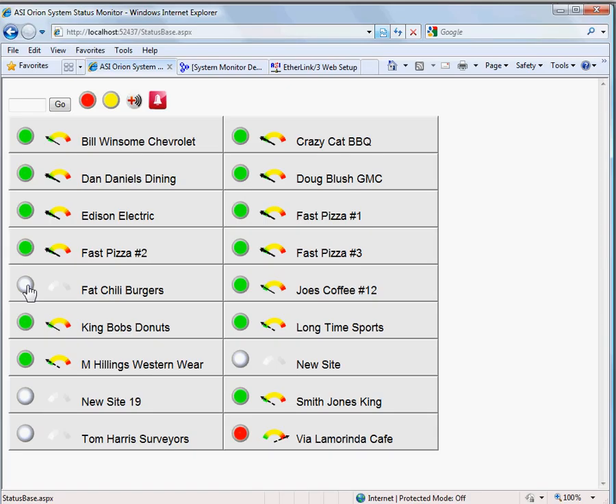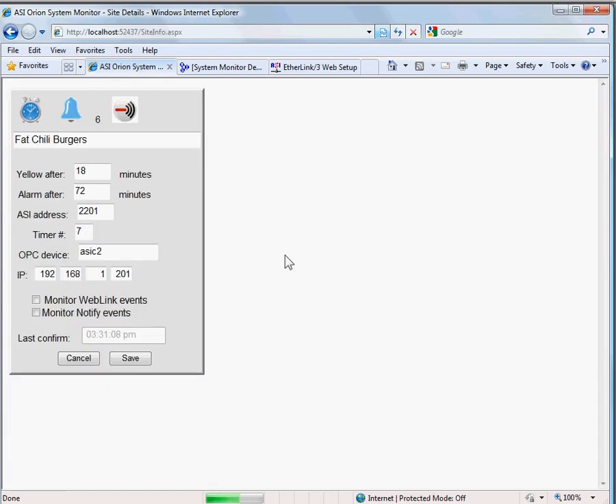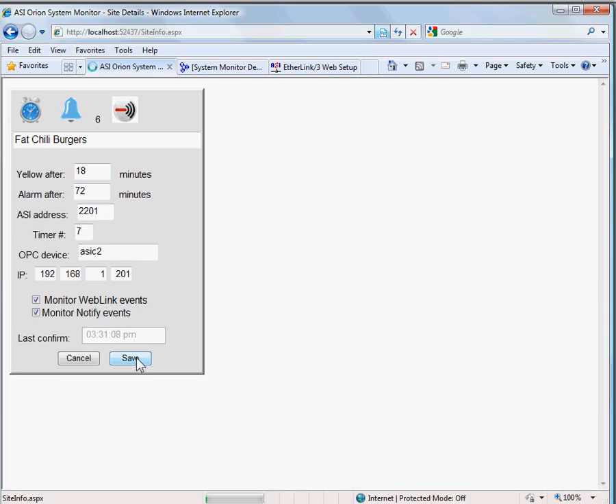We get a status right away. It's been a little while on Weblink, but the notify from the controller is pretty late because we've got some very tight parameters on this site. And what we'll do is trigger a manual notify event.